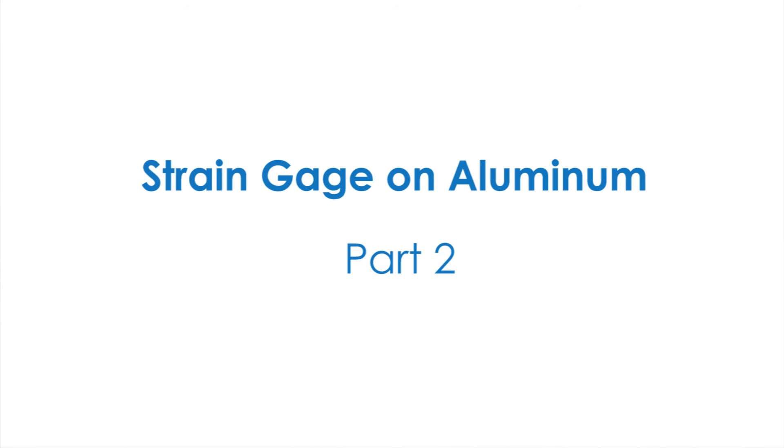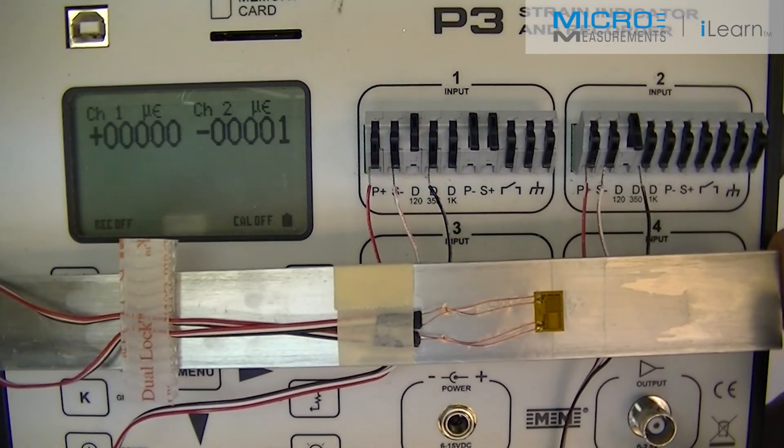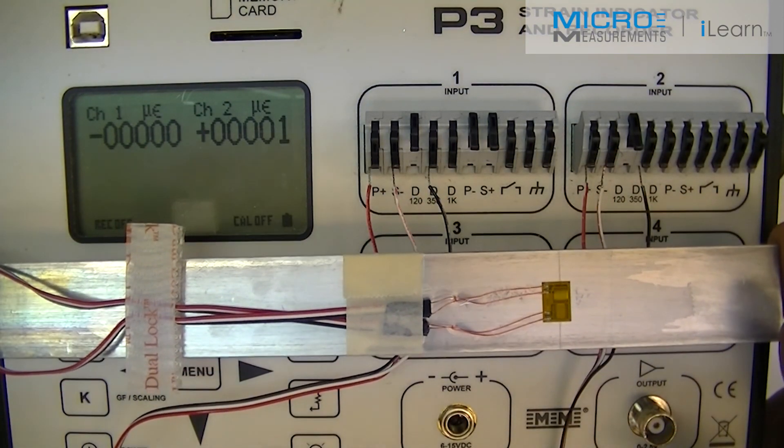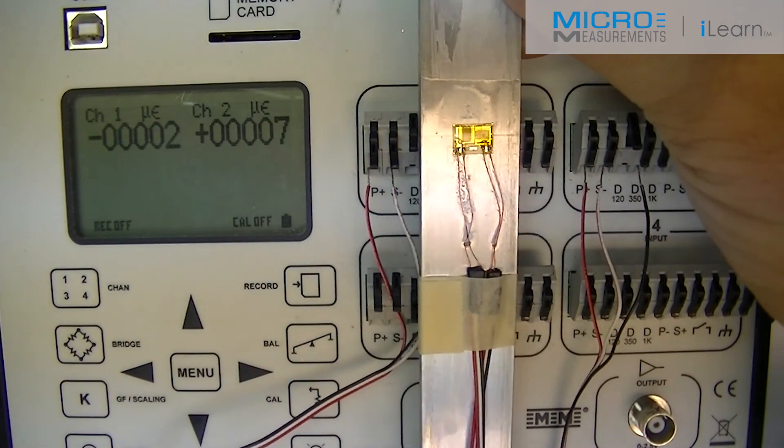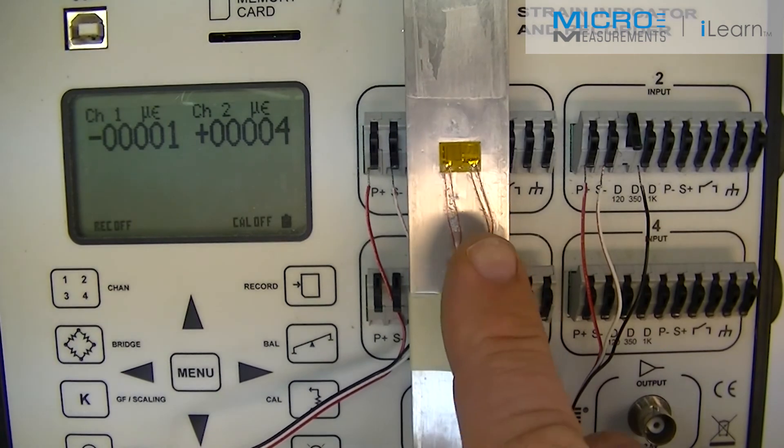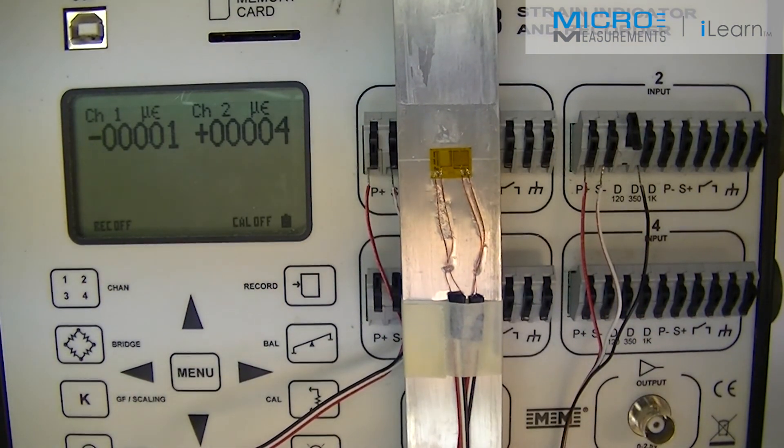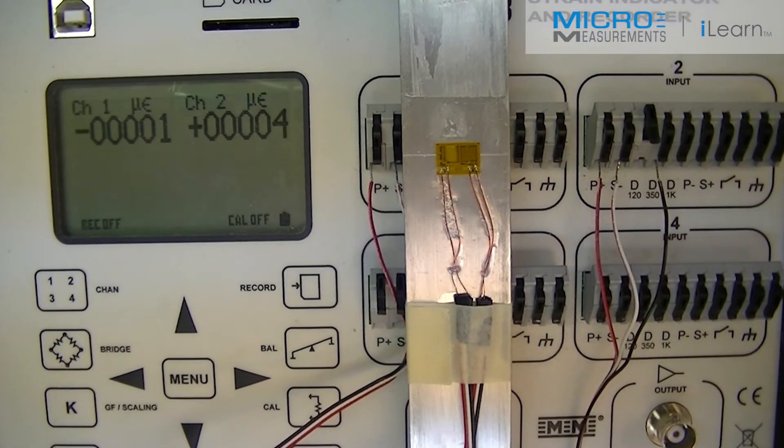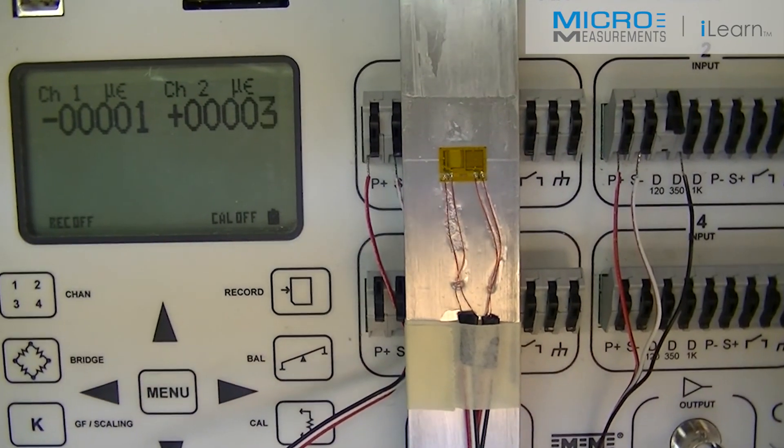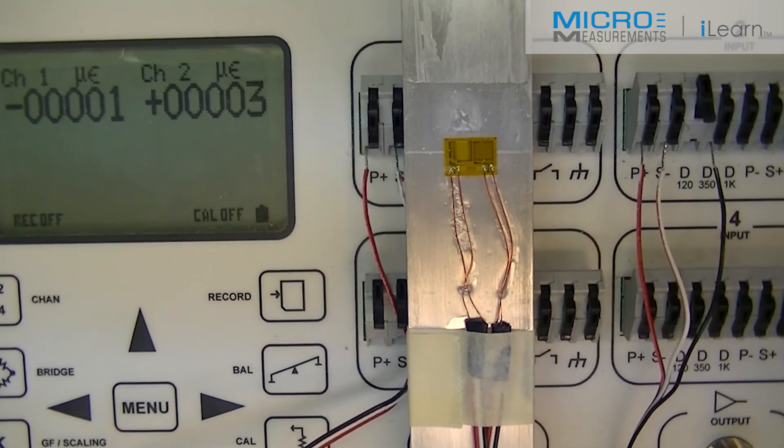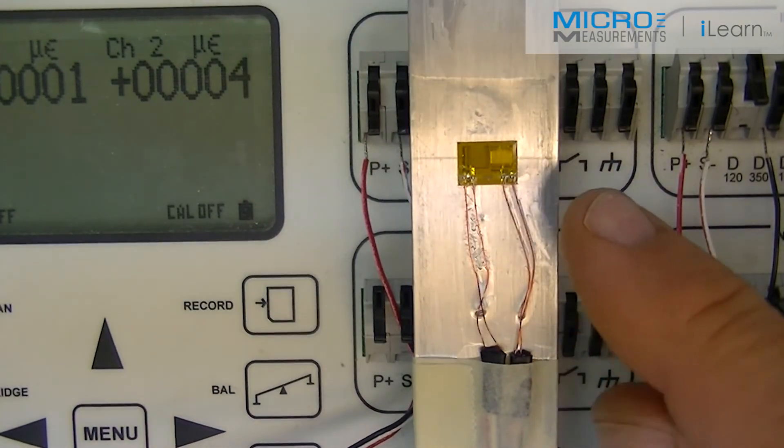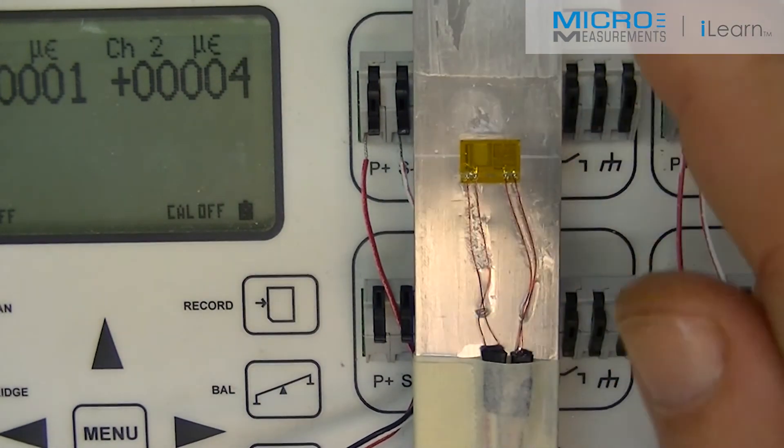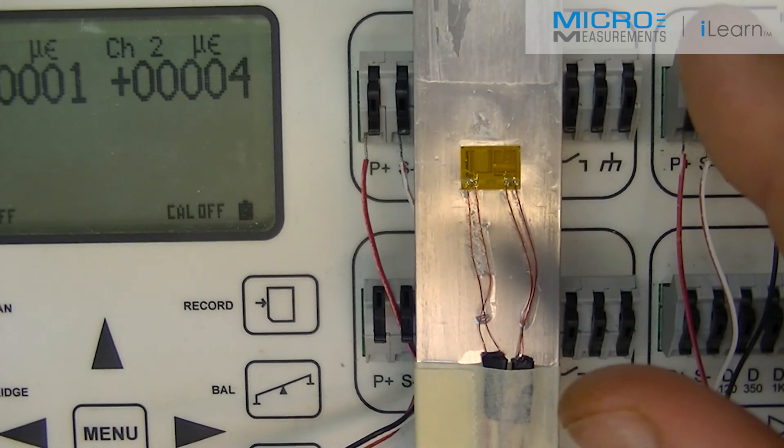Now we have our T-rosette installed and it's connected to the P3 strain indicator and recorder by Micro-Measurements. I just want to show that the grid on the left is called the Poisson grid. This is in this case the horizontal grid, measuring strain in the horizontal direction. The grid on the right is the linear grid that's measuring strain along the length of the beam.